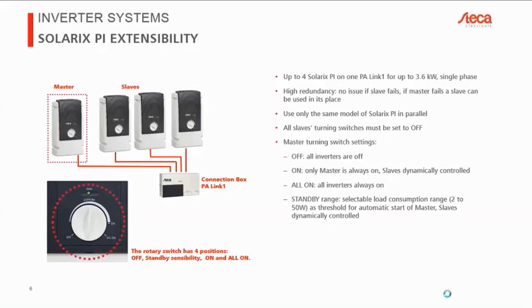So let's look at the SOLARIX PI extensibility. Here we have an example of a fully extended system with 4 SOLARIX PI inverters. And you can see here we have the connection box, the PA Link 1. So as soon as you're using more than 1 inverter, you will require this box. If you're using a single inverter, you do not require this box. So you can use a single inverter by itself without this box.